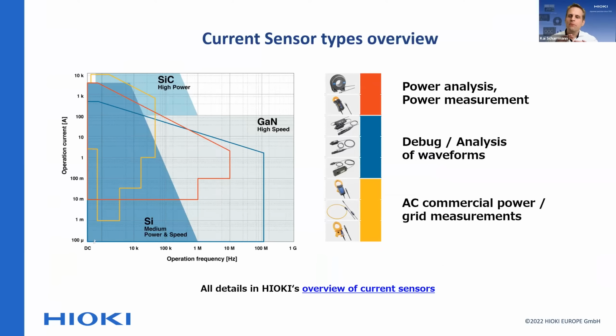Just to give you an overview of what kind of current sensors there are typically, we have about 3 different groups. One of them, the red ones, goes up until about 10 megahertz as a maximum, suitable for power analysis, and up to about 5,000 amps as a maximum.